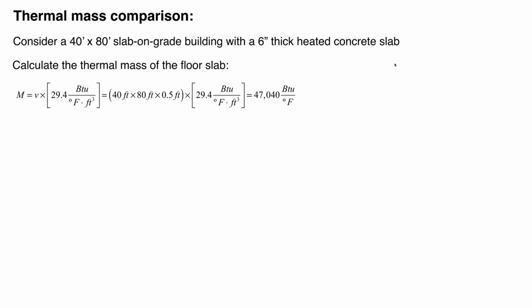Now, what does that mean? Well, it means it takes roughly 47,000 BTUs to change the average temperature of that slab by 1 degree Fahrenheit. Or another way to say it would be a 1 degree drop in slab temperature would release about 47,000 BTUs. And that's pretty significant.